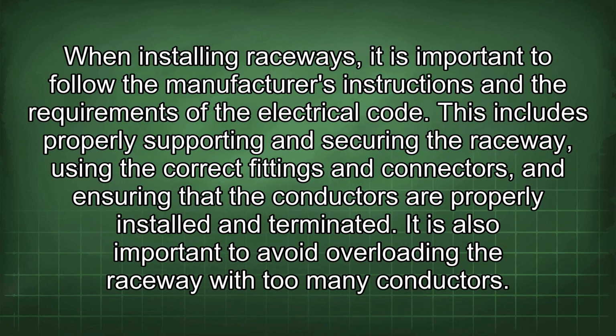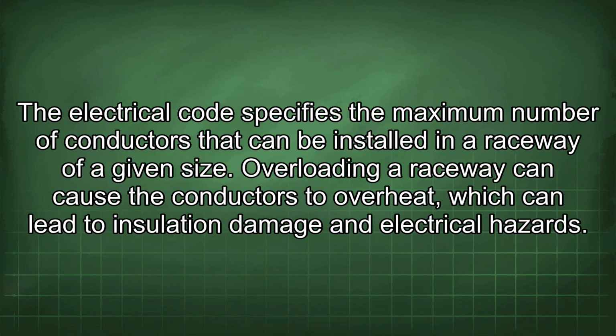When installing raceways, it is important to follow the manufacturer's instructions and the requirements of the electrical code. This includes properly supporting and securing the raceway, using the correct fittings and connectors, and ensuring that the conductors are properly installed and terminated. It is also important to avoid overloading the raceway with too many conductors. The electrical code specifies the maximum number of conductors that can be installed in a raceway of a given size. Overloading a raceway can cause the conductors to overheat, which can lead to insulation damage and electrical hazards.